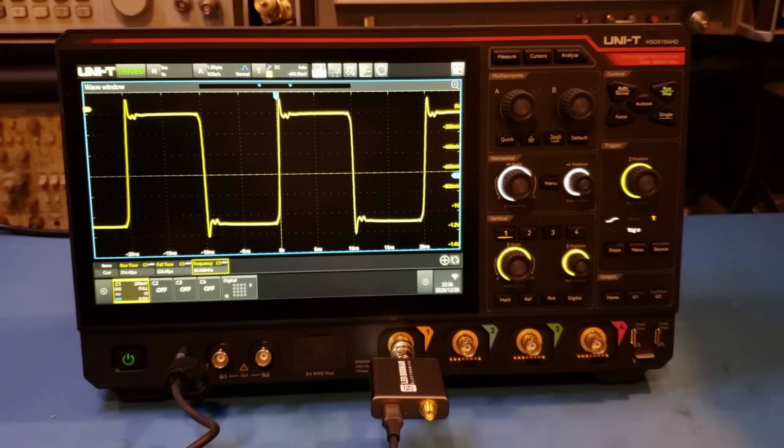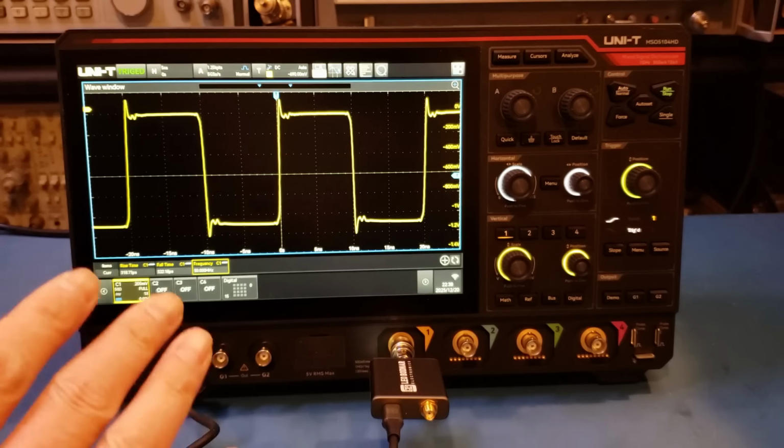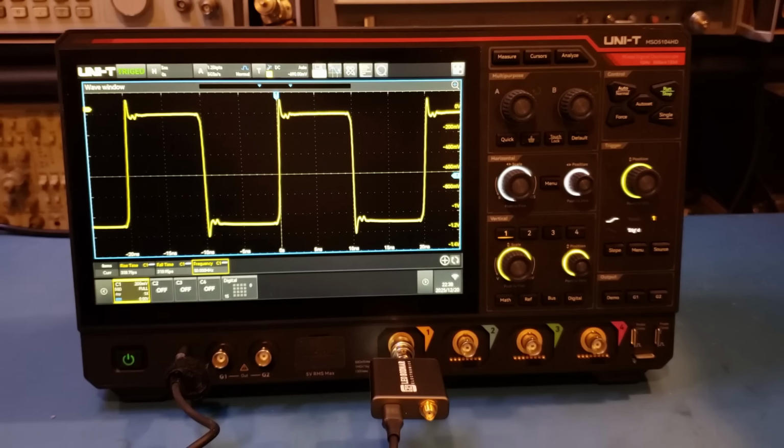Speaking of the rise time calculation, it depends on the digital filter implementation, whether it's a first order or second order digital filter. The calculation is, for example, 0.35 over rise time if it's a first order, or 0.45 over rise time if it's a second order. Now for this UNI-T, you can see that the manufacturer's official number is using the 0.35 factor. Again, I usually use the 0.35 factor as a first order approximation, and the obtained bandwidth should be in the ballpark. Of course, if you know the actual implementation details of the filters, you can adjust the factor accordingly.